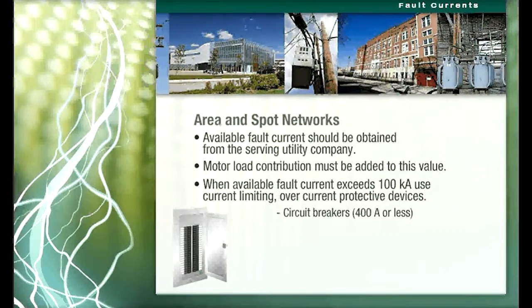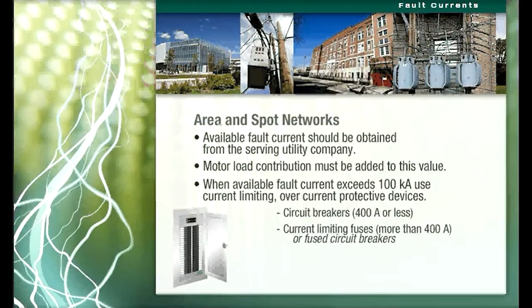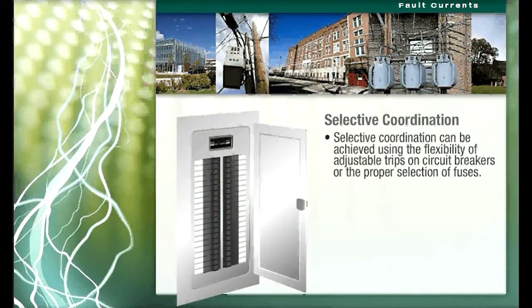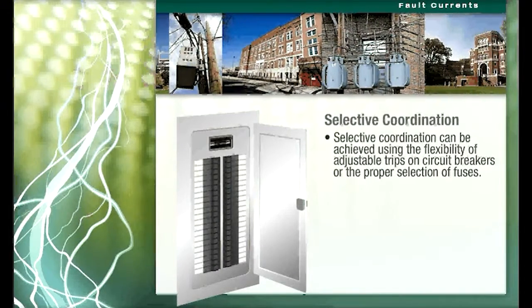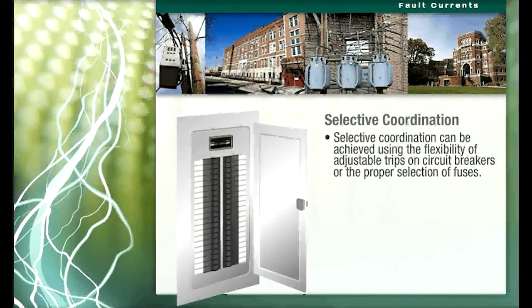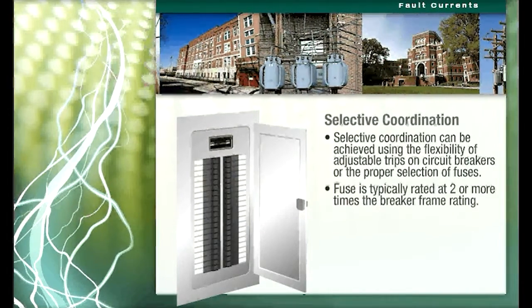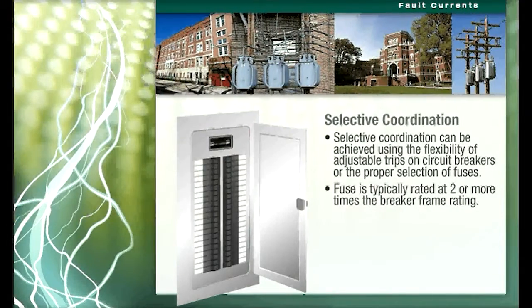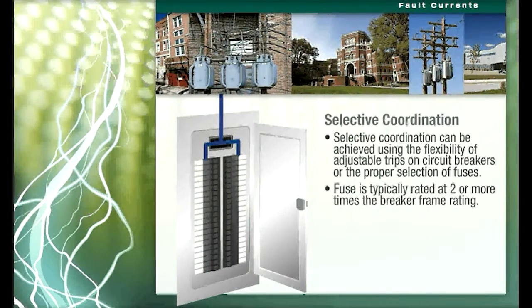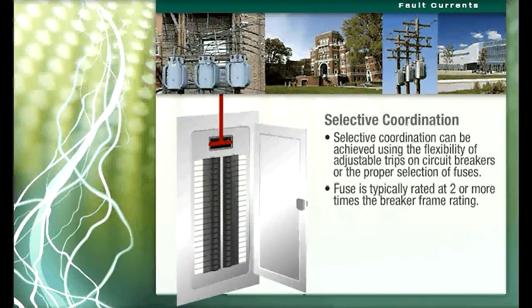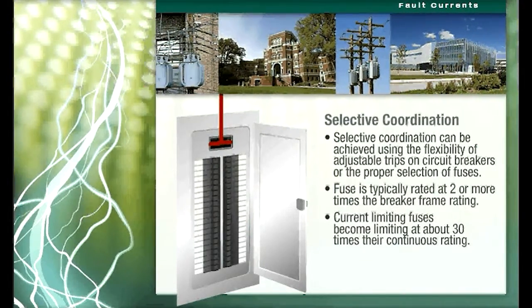For circuits rated more than 400 amps, current limiting fuses are used. The common practice is to use fuse-circuit breaker combinations. Selective coordination can be achieved using the flexibility of adjustable trips on circuit breakers or the proper selection of fuses. When the combination of fuse and breaker are used, the fuse is typically rated at two or more times the breaker frame rating, so its rupture point is above the breaker trip value for all but the most severe faults. For current limiting fuses, they become limiting at about 30 times their continuous rating.